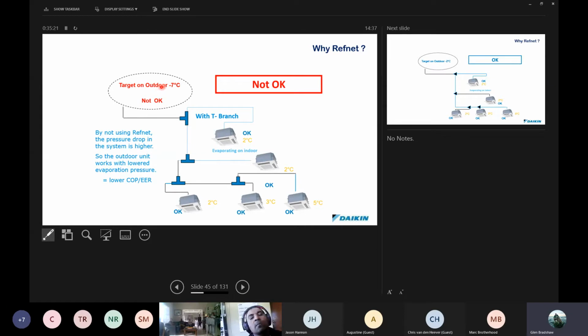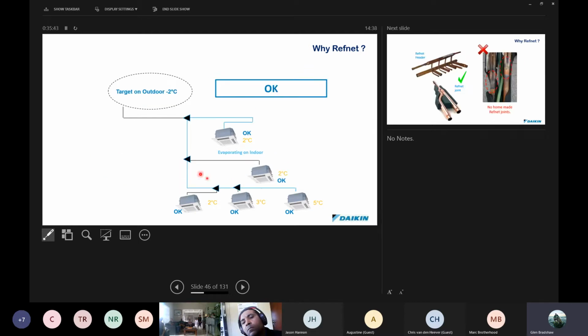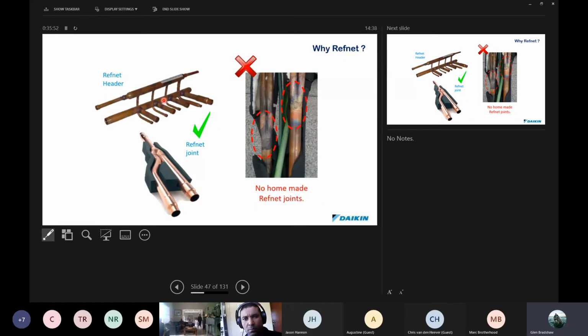So you find that the target outdoor condition might be going down to -7, which is not okay. If you're not using Refnets and are using T-pieces, the flow is not even in the system. It's not equal, and this causes the system to have an imbalance of temperatures. If we use Refnet joints, which is what this symbol denotes, we get a much more even flow and our target condition of -2, which is much better.